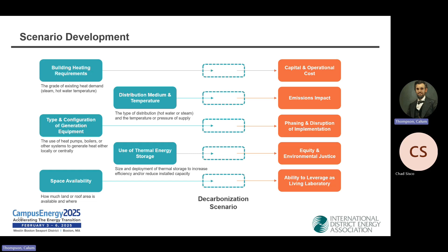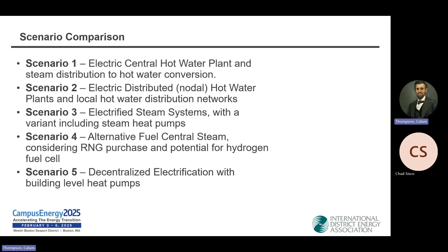The 5 scenarios we evaluated in detail were a transition from a steam central plant to a hot water central plant, and multiple subversions of that; the ability to do nodal central plants, essentially breaking out districts of the campus to develop a solution for those; maintaining the steam network but electrifying the central source through electric boilers or steam heat pumps; an alternative fuel option, again maintaining steam as the medium; and the complete decentralization of the thermal network, certainly on the heating side, to locally generate it.